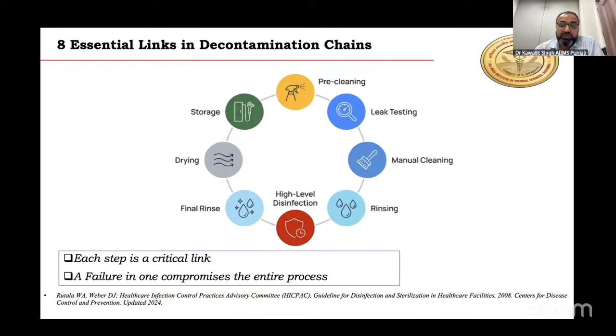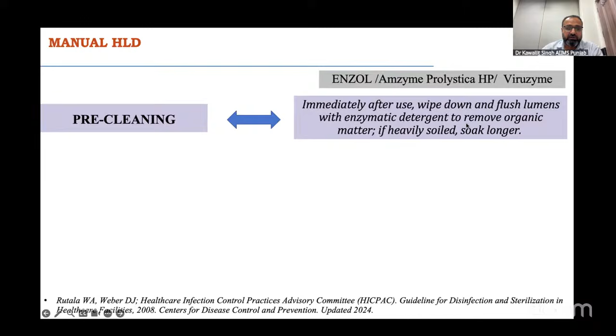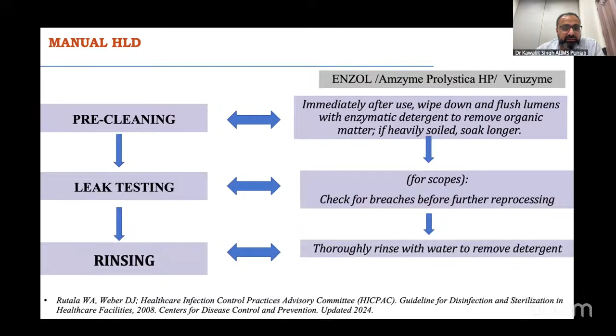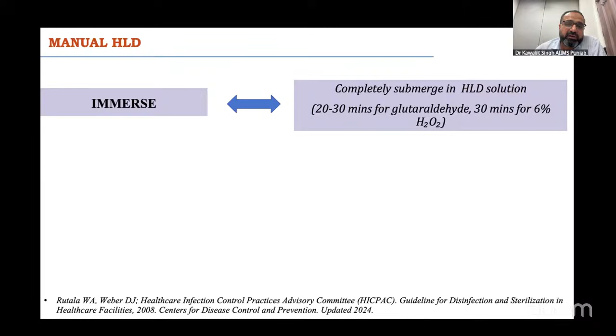Immediately after use, we wipe down and flush the lumens with these solutions and remove the organic matter. And if heavily soiled, we soak them for a longer time. This is followed by leak testing, already described, and rinsing thoroughly to remove the detergent. The next step is immersing into the solution, and that is, we need to completely submerge the scope into the high level disinfectant solution for 20 to 30 minutes. In the next few slides, I will describe the different parameters that have been given for the different solutions that are currently available with us.